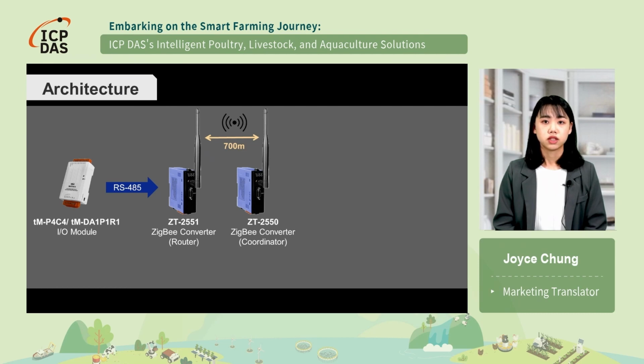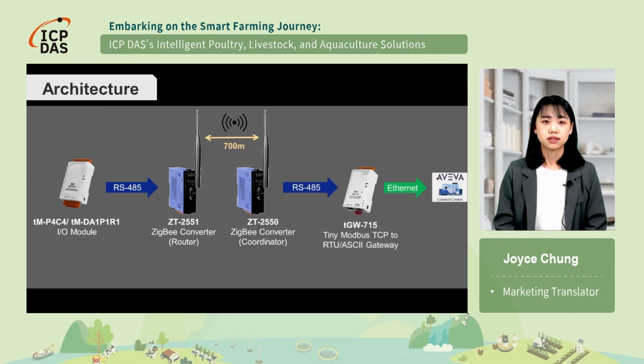The combination of the Zigbee converters extends the transmission distance and avoids the complex wiring problems out in the field. Then the data is sent to the control center for further analysis through the TGW715 gateway, which converts the communication protocol from Modbus RTU to Modbus TCP.